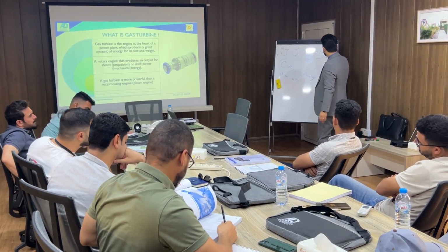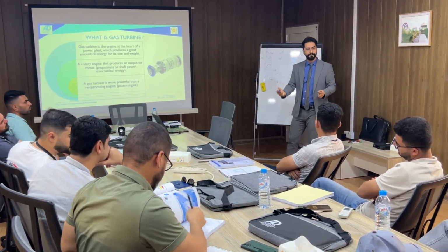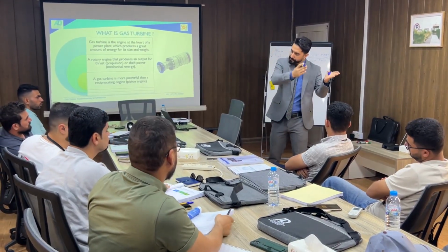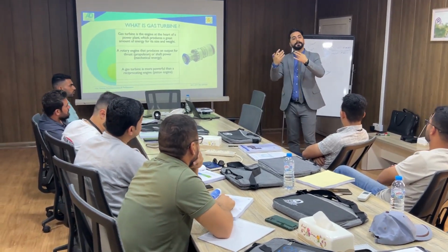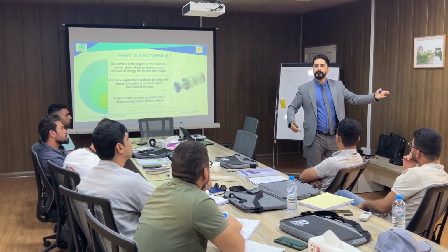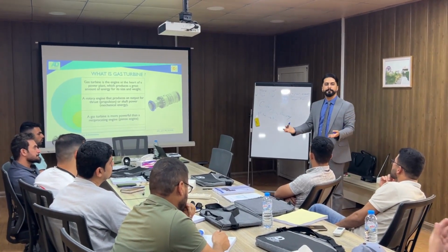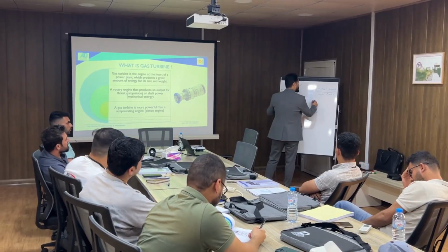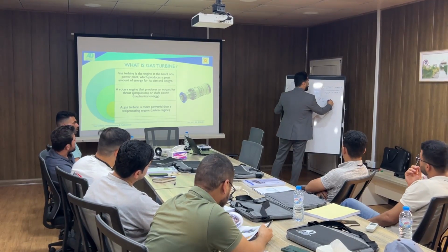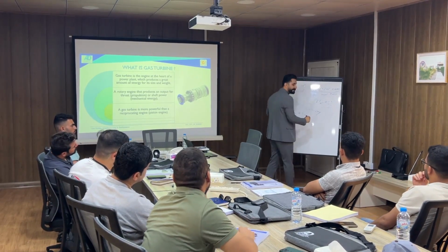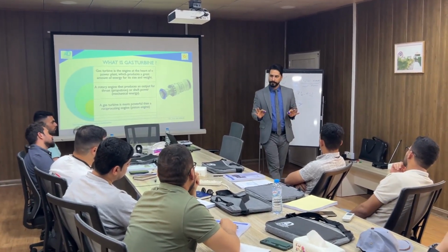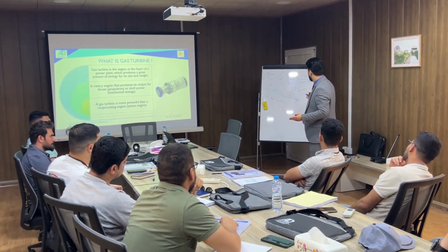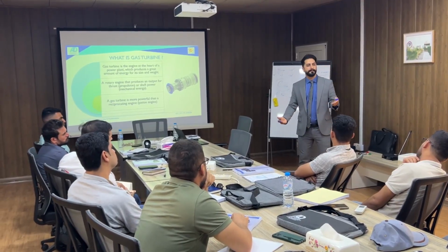And the output energy can be in different ways. If we use a generator in the gas turbine, we are going to change the work to the electricity. So the amount of electricity in comparison to the amount of heat which is used, it can be the effectivity. And normally when we are going to talk about gas turbines, about 25 till 45% of the effectivity is desired. It means that at the first step, we are going to consider about 55 or 75 of waste of energy.